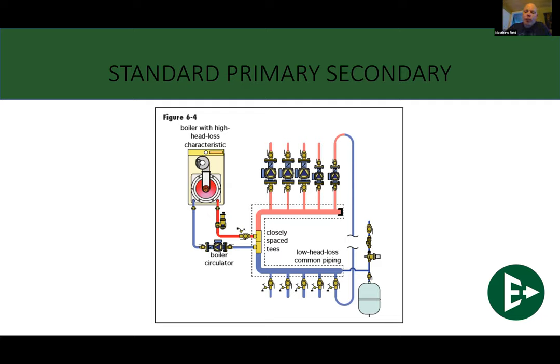One of the questions they get for closely spaced tees a lot is they're designed to be placed no more than four pipe diameters apart from each other. But you cannot place them too close together. So forget that four pipe diameters apart. Just put them side by side. Put them as close together as you possibly can, and you're not going to have any problems at all with regards to your primary secondary circuit piping. If you're worried about making it too far apart, don't. Just put them as close together as you can, and that's how you want closely spaced tees to work.